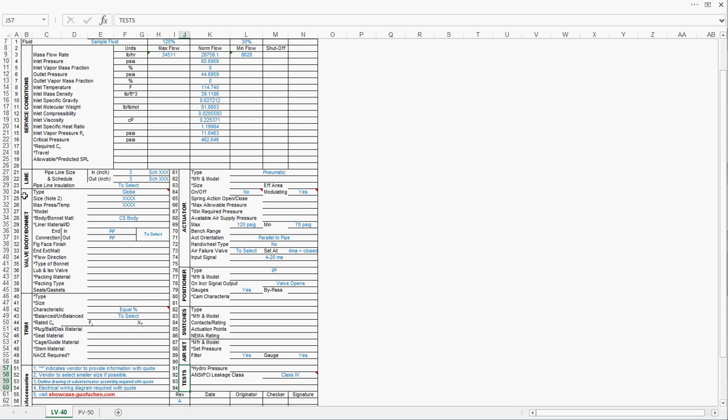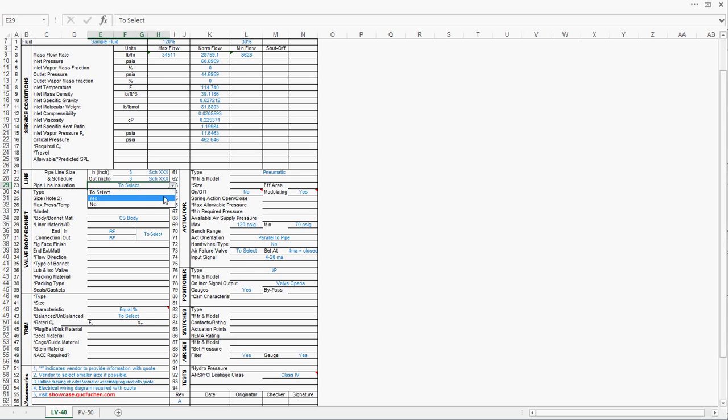Let us first take a look at the line section. Permax automatically filled out the pipe size. If you know the pipe schedule, you can put it here. If you don't know, that's totally all right. Regarding the pipeline insulation, since we are talking about 115 Fahrenheit operating temperature, it is not necessary to have pipeline insulation.